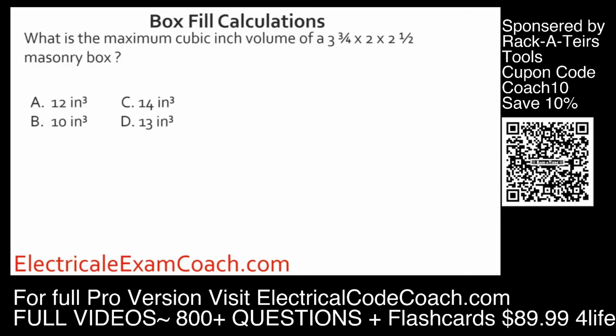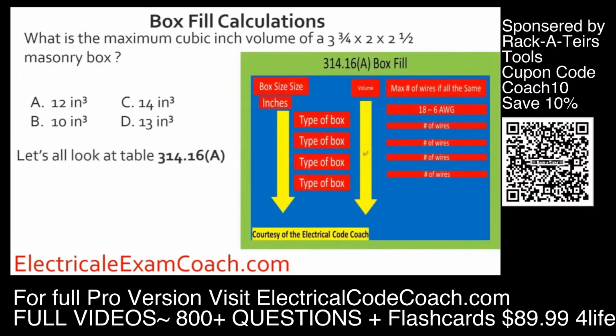What is the maximum cubic inch volume for a 3 3/4 by 2 by 2.5 masonry box? For this one, we're going to head to 314.16(A), and we're going to use that middle column, that volume column. We come down, we look very closely, and we find that it's 14 cubic inches. This is very important that we understand this process before we move on into more complex box fill calculations.